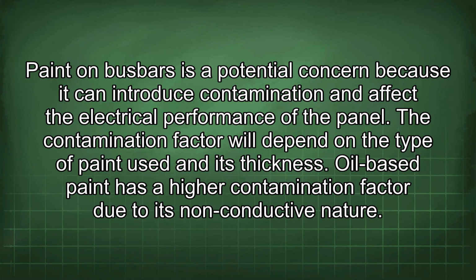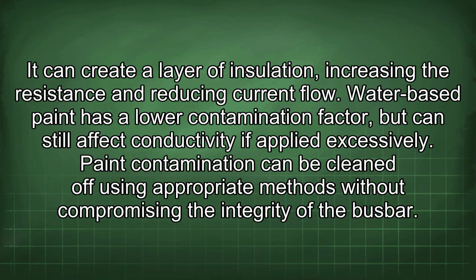Paint on busbars is a potential concern because it can introduce contamination and affect the electrical performance of the panel. The contamination factor will depend on the type of paint used and its thickness. Oil-based paint has a higher contamination factor due to its non-conductive nature. It can create a layer of insulation, increasing the resistance and reducing current flow.